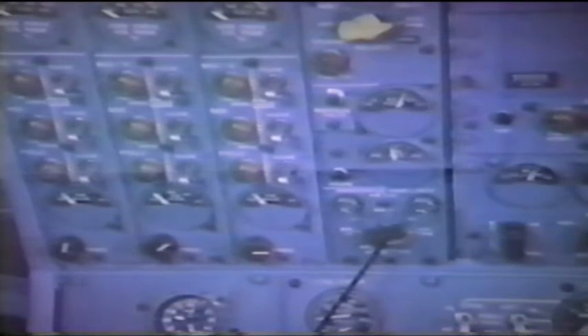We have to observe the synchronizing lights, which are in the lower right-hand corner of the electrical system. And these will be blinking together. And when they are blinking, they are reflecting a difference of cycle, a difference of phase between whatever you have selected on your AC meter switch and whatever is powering the tie bus. So if we have 2 generators already tied into the tie bus, and we have the 3rd generator, we'll say generator number 3, which we would like to manually parallel to the tie bus, we select generator number 3 with the AC meter selector, and now when the lights are on, it means that generator number 3 is not in phase with generators 1 and 2, which are paralleled on the tie bus.